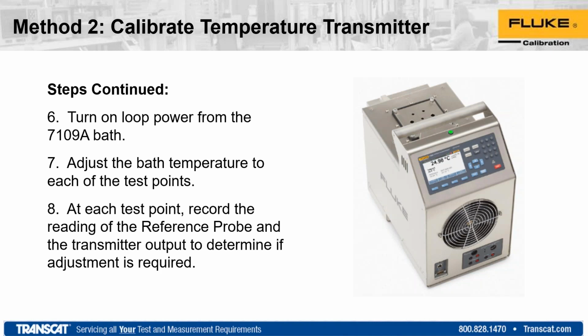All right, here's where we go into the bath. You turn on the loop power in the process option setting, as well as activate your reference probe. In this example, they said adjust to each of the different set points. You can do that as well, or again, you could run the pre-programmed points of, say, a previous program if you do the same one over and over. So it would go to your test point, ramp up, stabilize, soak. That'll give you some time to gather the data. And then once it's gone past that soak point, it'll continue on and ramp through the various testing points.